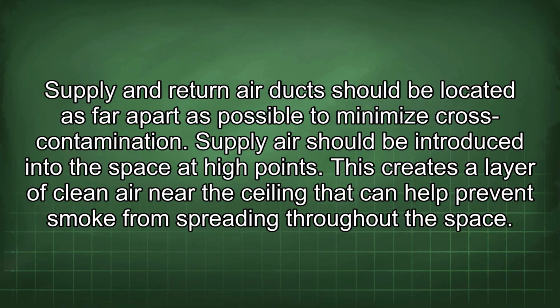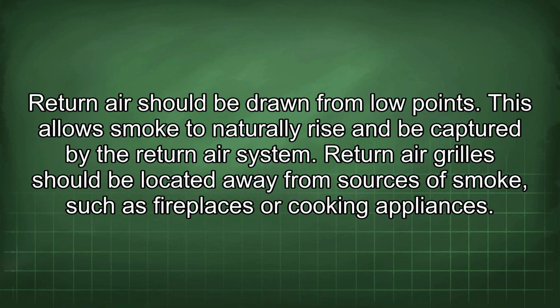Supply air should be introduced into the space at high points. This creates a layer of clean air near the ceiling that can help prevent smoke from spreading throughout the space. Return air should be drawn from low points. This allows smoke to naturally rise and be captured by the return air system. Return air grills should be located away from sources of smoke, such as fireplaces or cooking appliances.